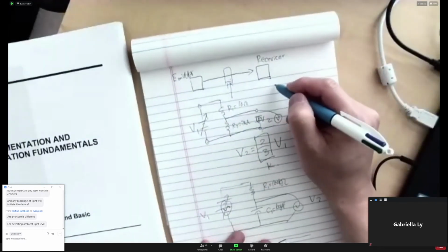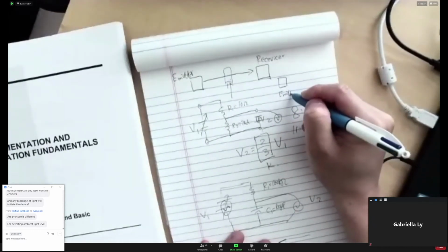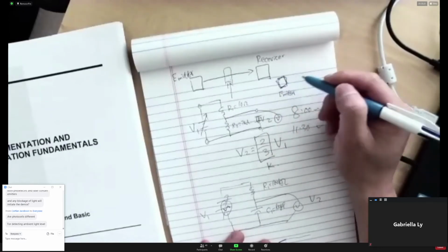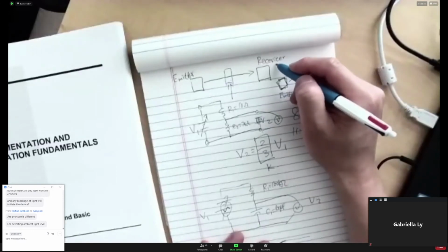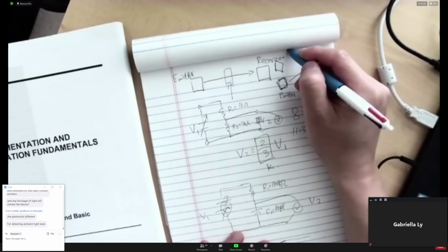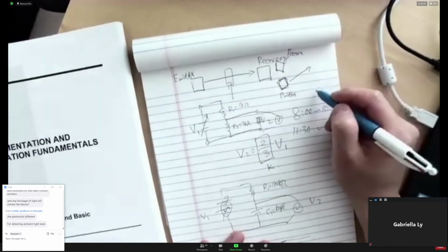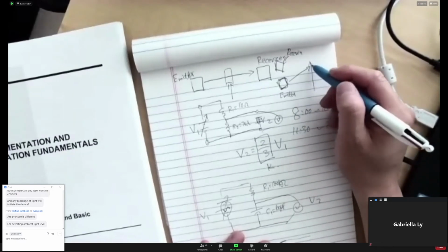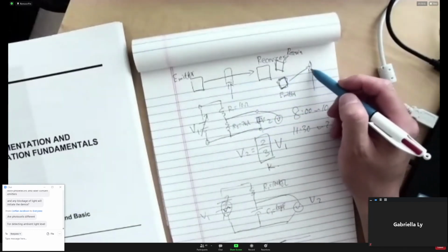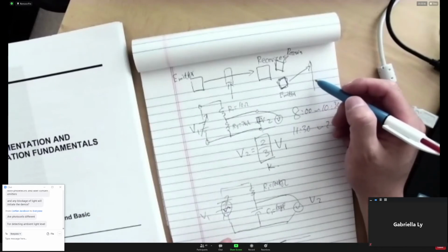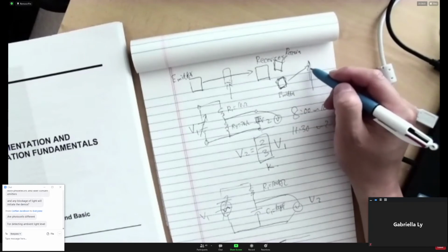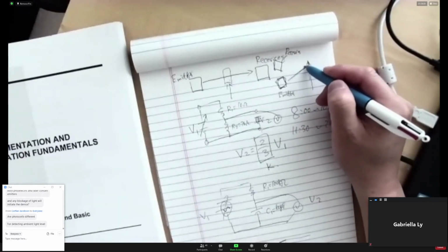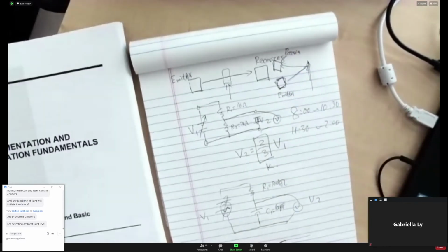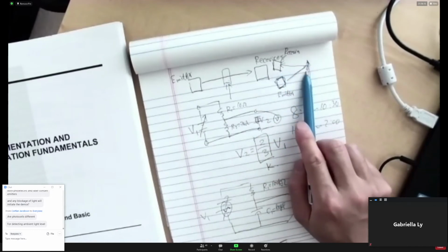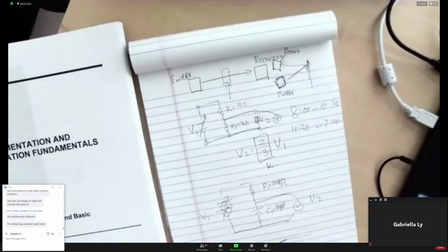And another type is you have an emitter here, but this emitter is put in at an angle. It will give out a light. Then you will have a receiver here. So here is the material passing through. It depends on the application. With those, you usually have the material with a shiny reflective surface. So when you have a piece of material passing here, the light the emitter sends will be reflected through to the receiver. That's where they can detect if there's a material here or not. So different application, different ways.